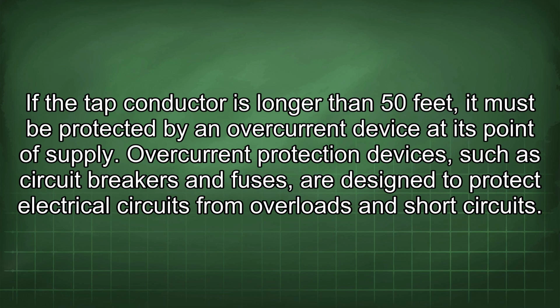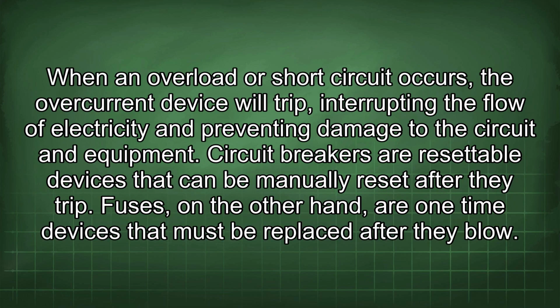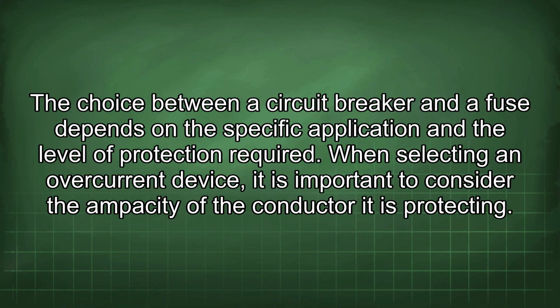Overcurrent protection devices, such as circuit breakers and fuses, are designed to protect electrical circuits from overloads and short circuits. When an overload or short circuit occurs, the overcurrent device will trip, interrupting the flow of electricity and preventing damage to the circuit and equipment. Circuit breakers are resettable devices that can be manually reset after they trip. Fuses, on the other hand, are one-time devices that must be replaced after they blow. The choice between a circuit breaker and a fuse depends on the specific application and the level of protection required.